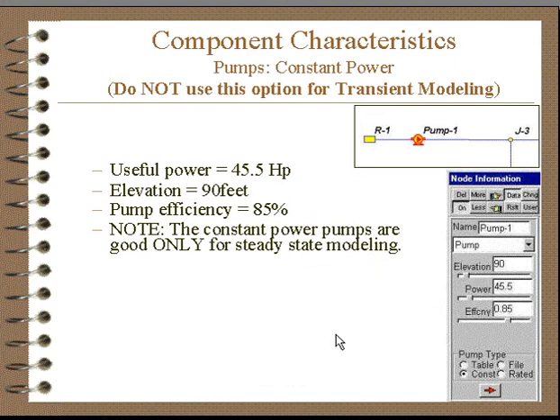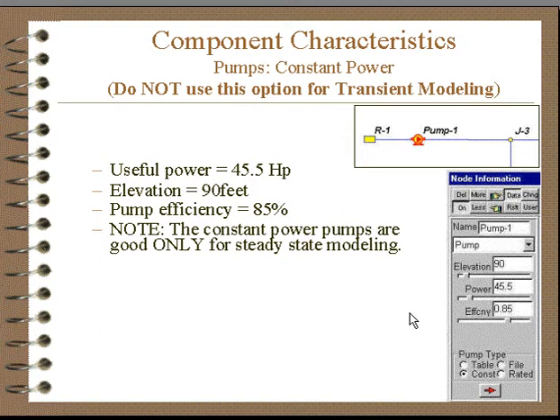For transient modeling, we should not use constant power pumps. We don't have the characteristics needed to relate the speed to the operating conditions, and therefore these types of devices are not appropriate for transient modeling.